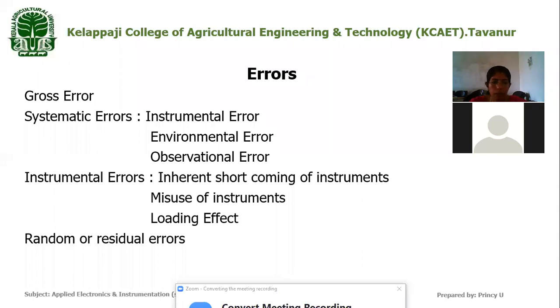So proper calibration should be done, and that calibrated reading should be marked on the meter itself by the manufacturer to overcome this error. Okay, this error may cause the instrument to read too low or too high a value, and this error may be caused due to friction or hysteresis, etc. So due to changes in frictional value and hysteresis value, that error will be present in that instrument. So we have to calibrate that instrument with a standard instrument, and by comparing we can find out the value. To get the accurate value, we have to add or subtract some calibrated value to that instrument. So that comes under systematic error.